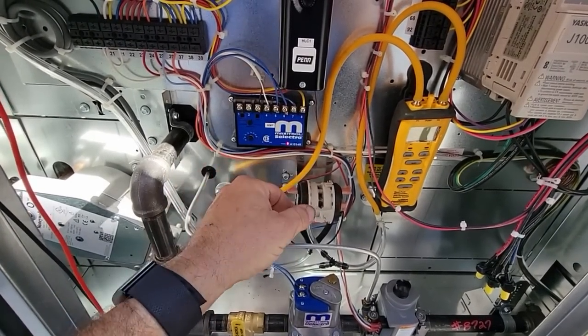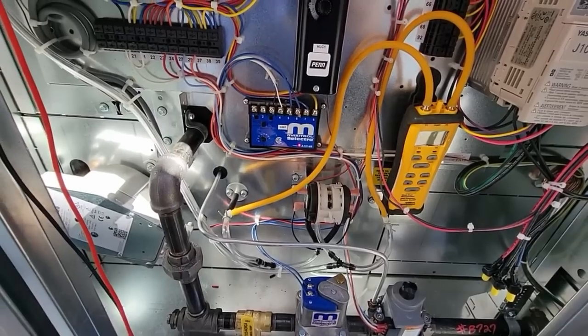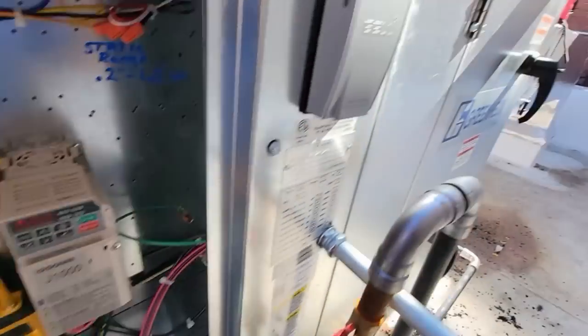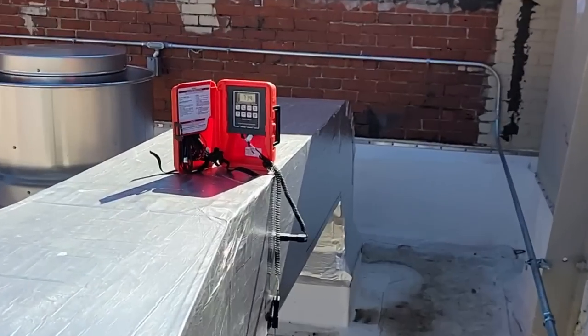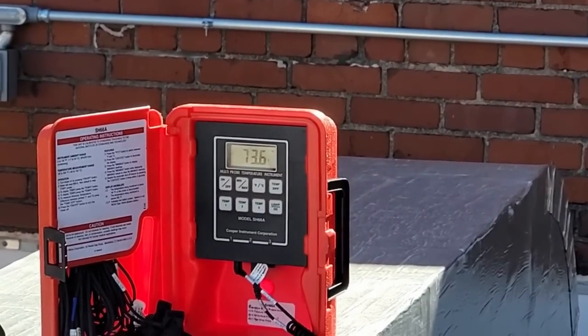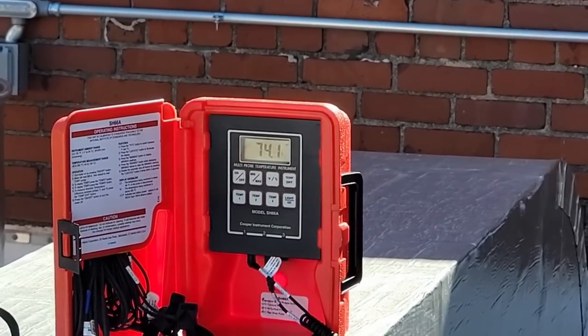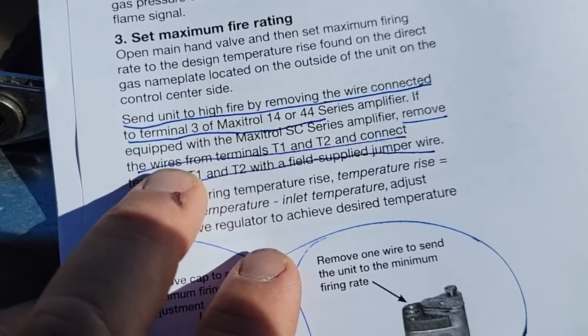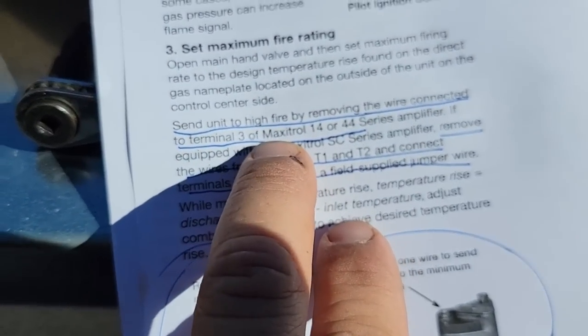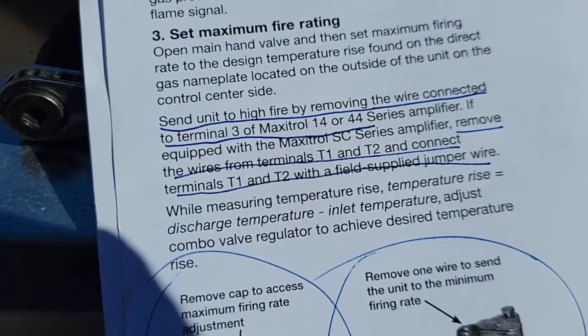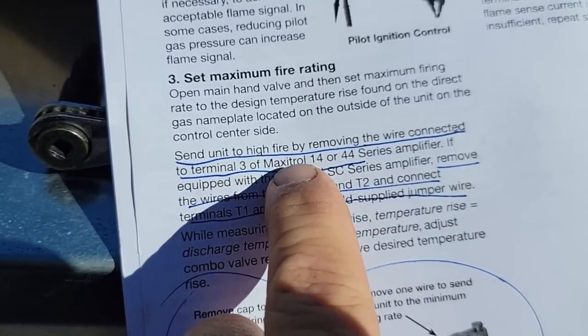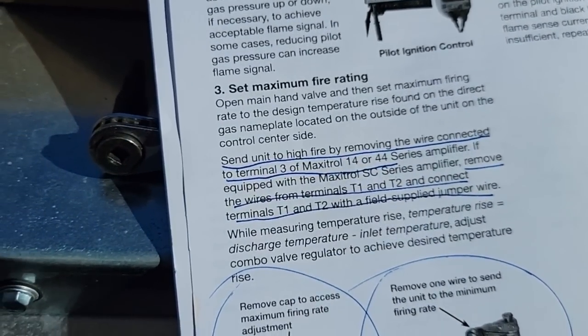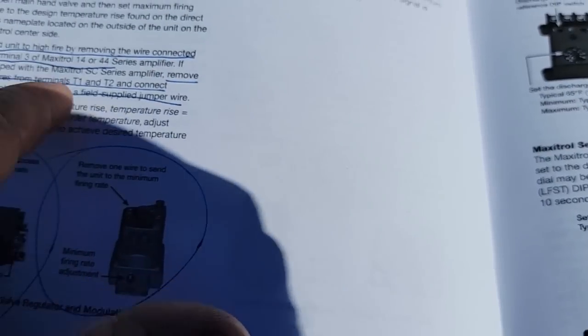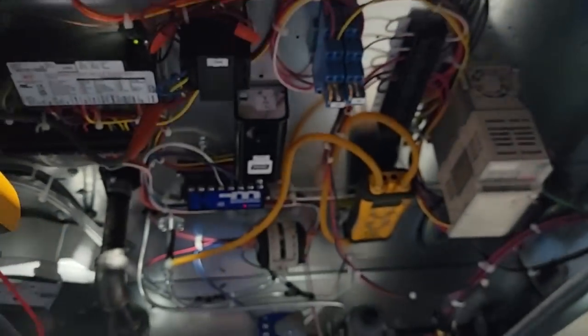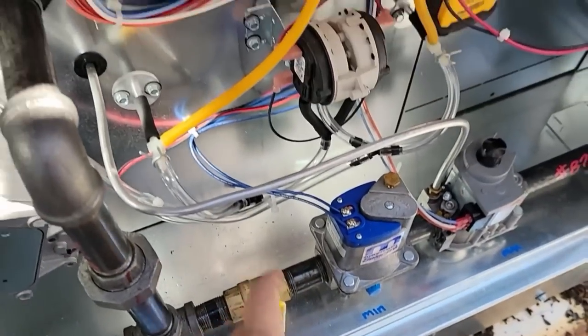If we turn that on, it'll get crazy up in this mug. There she goes. Look at our heat. Should probably start changing there. Maybe, maybe not. Yeah, it's going up to the minimum. We're gonna go ahead and put this thing into maximum fire. So like it says right here, remove the wire connected to terminal 3 of the Maxitrol 14 or 44 series amplifier. 14, that's what this one is. So terminal 3, remove it. Let's go ahead and kill the main valve first so we don't overheat it.